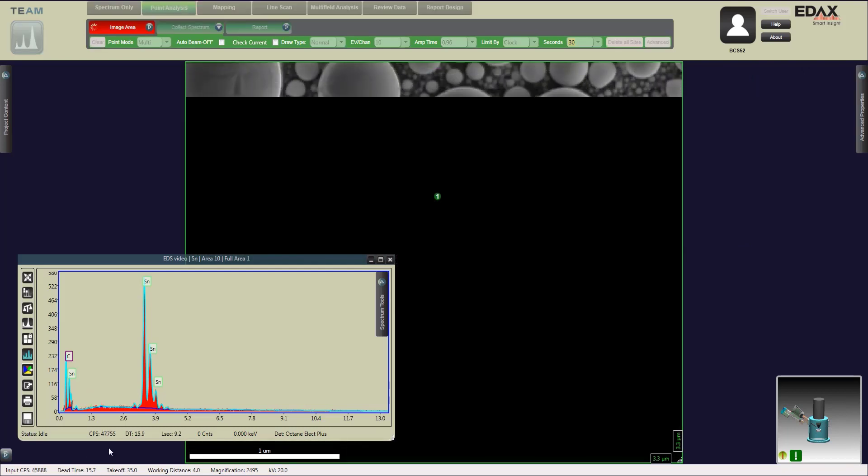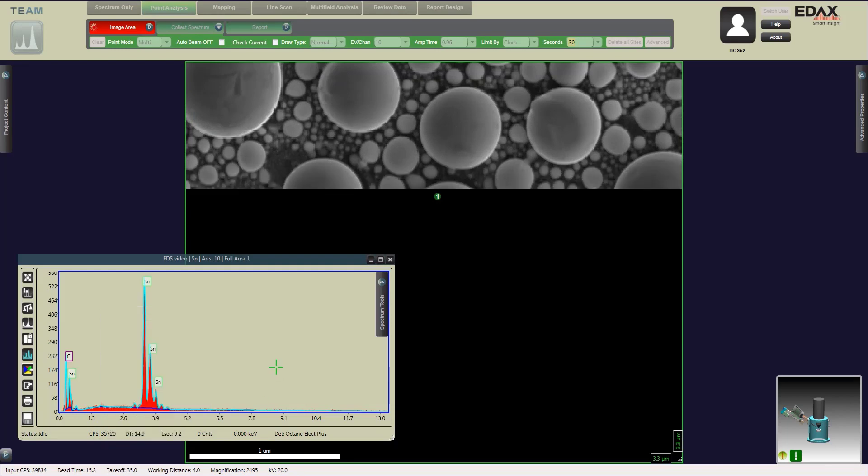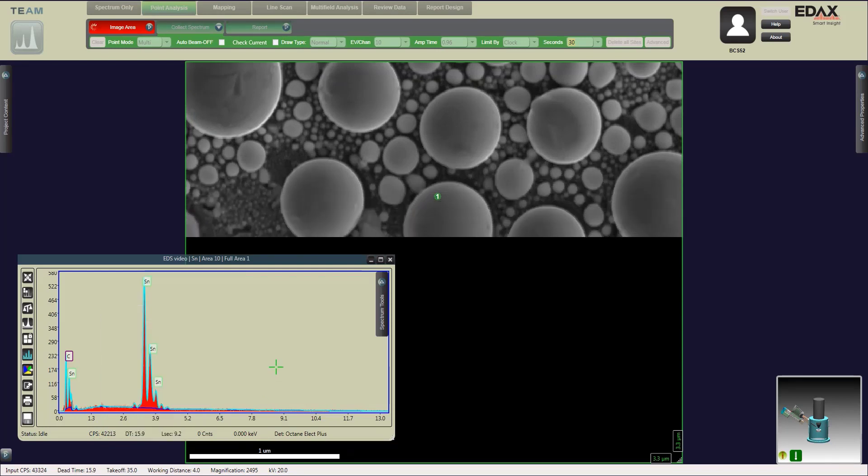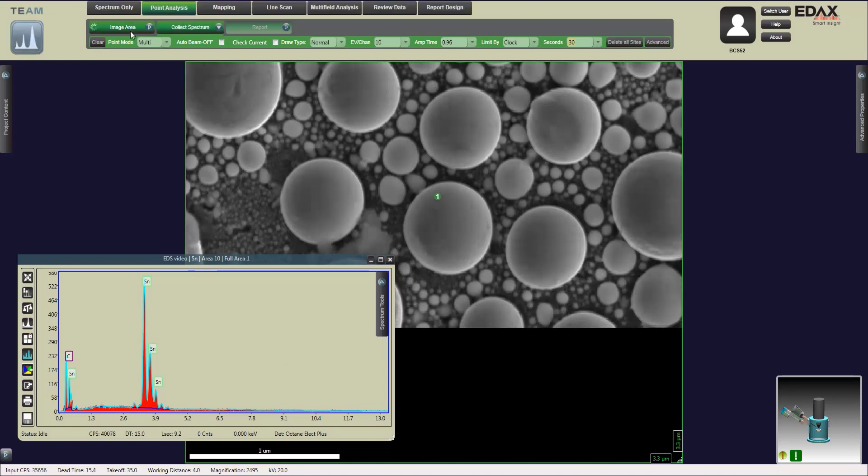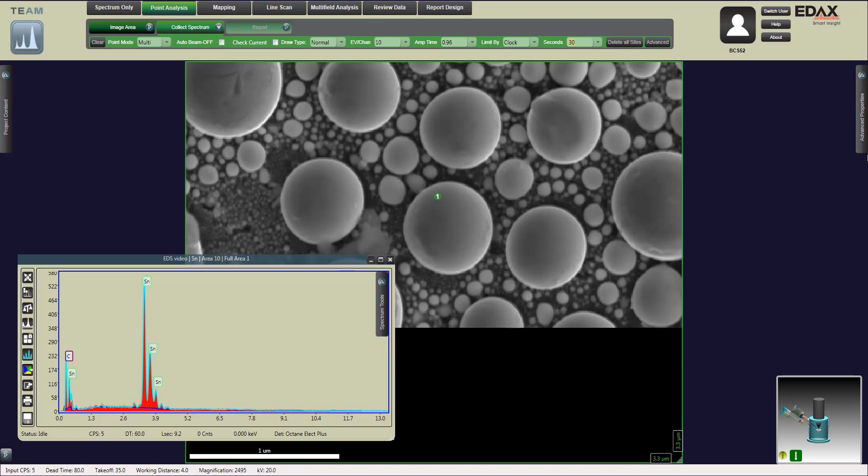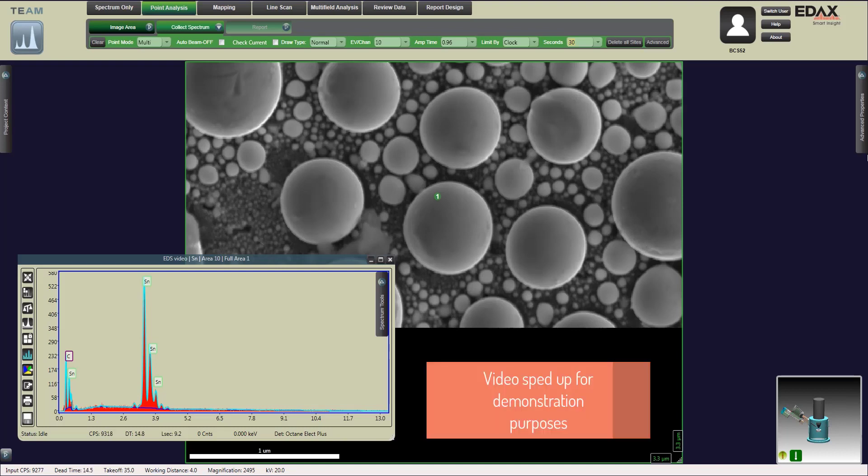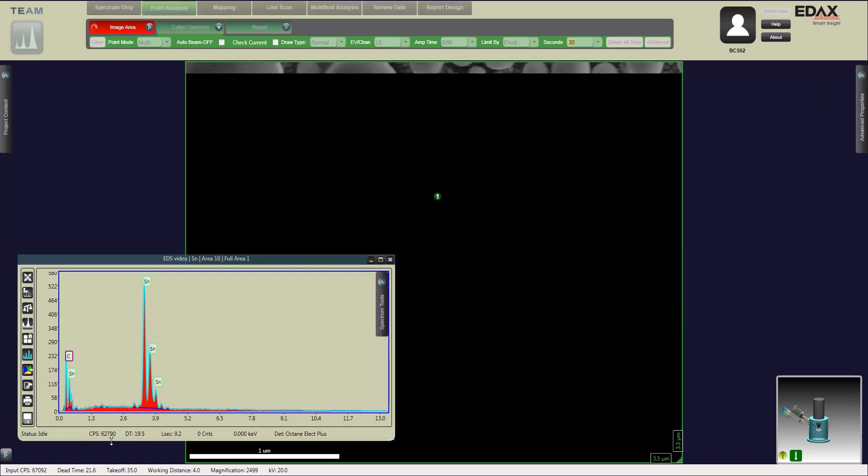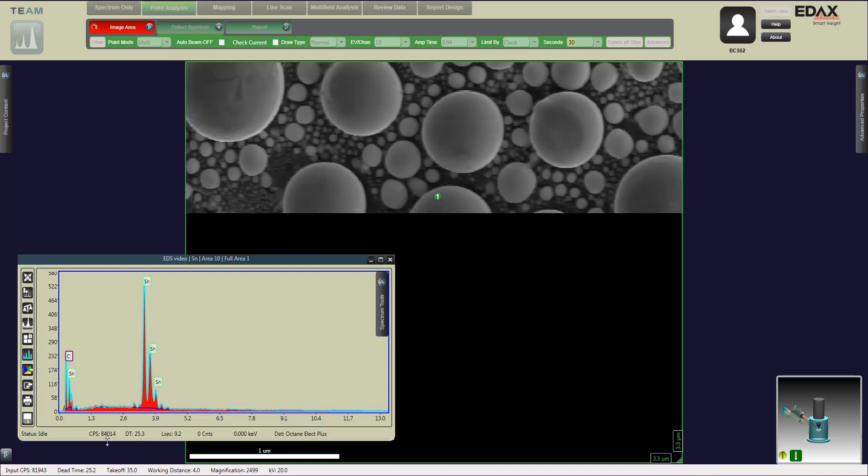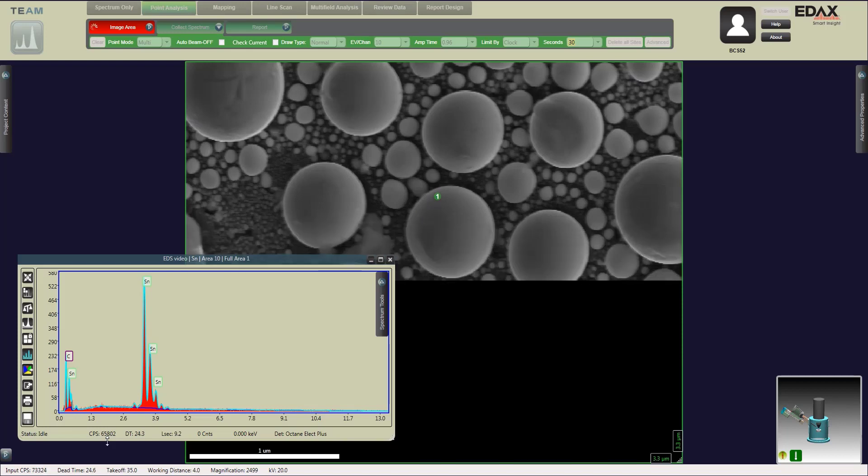Now I'm going to re-image the area. We can look we're at about 45,000 counts per second. Still want to get a little bit higher. We're shooting for about 70,000 counts per second when we're doing a spectrum scan, and we'll shoot for about 100,000 counts per second when we're doing mapping. I'm going to go back to the other PC and increase the current one more time until I get to the range that we're looking for. Let's change the current again, re-image the area, and now we're right about 70,000 counts. It's going to fluctuate a little bit. It's always material dependent.